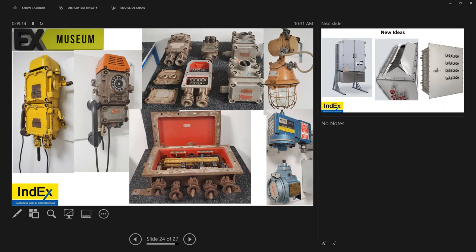Are gas groups based on minimum ignition temperature? Note, this is not the same as equipment group as stated. Yeah, so it's based on its minimum ignition energy and its LELs and UELs. There are many different considerations, but it's ignition energy and also its temperature class. It depends on what gas it is, but usually it's minimum ignition energy.